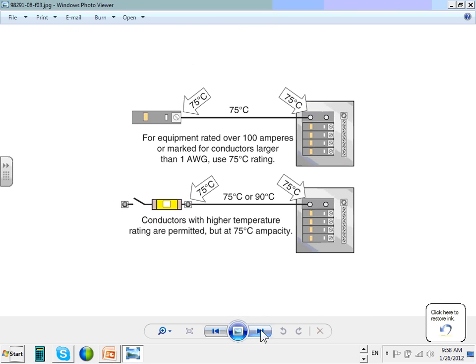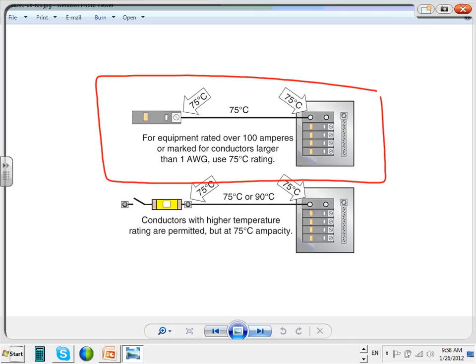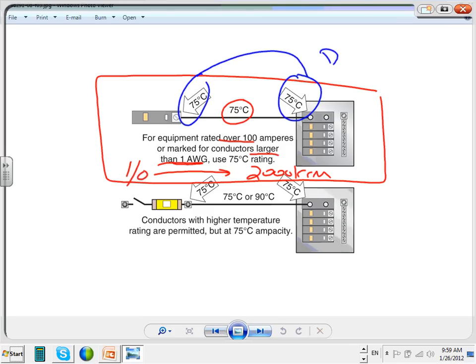So that's basically the thought. The second rule, please remember that one. This also applies if the amps are over 100 or the conductors are larger than number 1. Larger than number 1 will get you from 1/0 all the way to 2000 kcmil. Is that the highest that we can get in the table? Yeah, 2000 kcmil, you're going to go to 75. Granted, the cable has to be 75. If I put a 60-degree rated cable here, it shifts you all the way to 60, the weakest link. But by design, by default, this is the default.